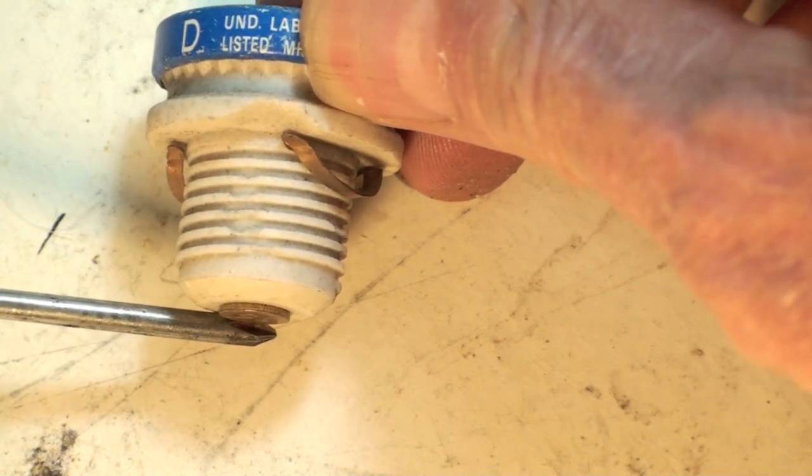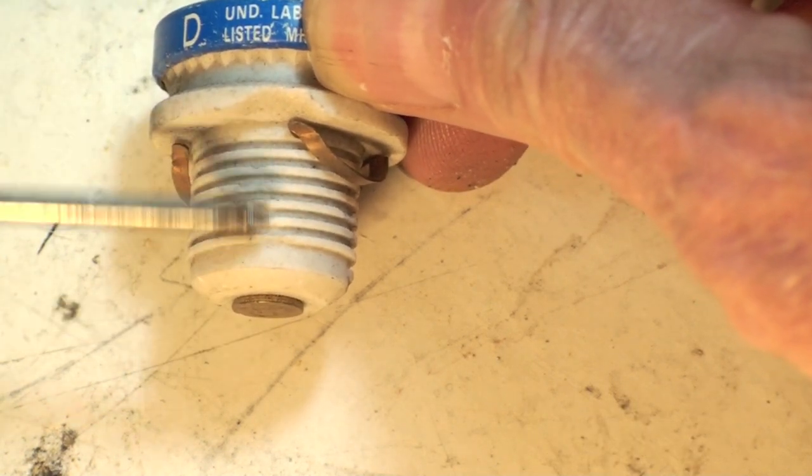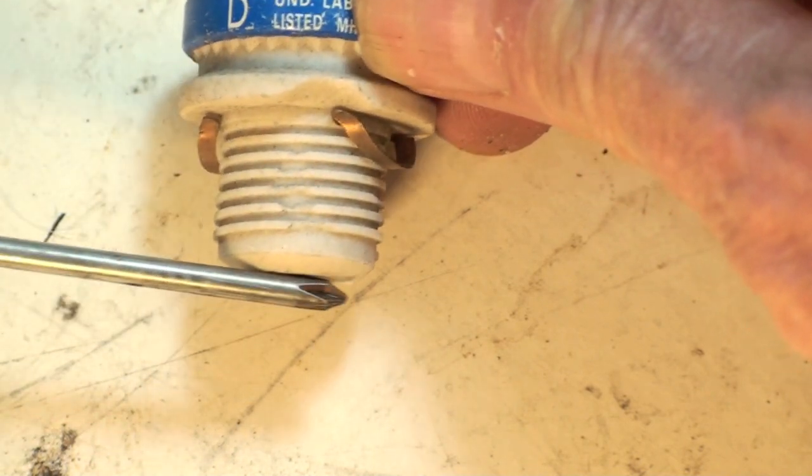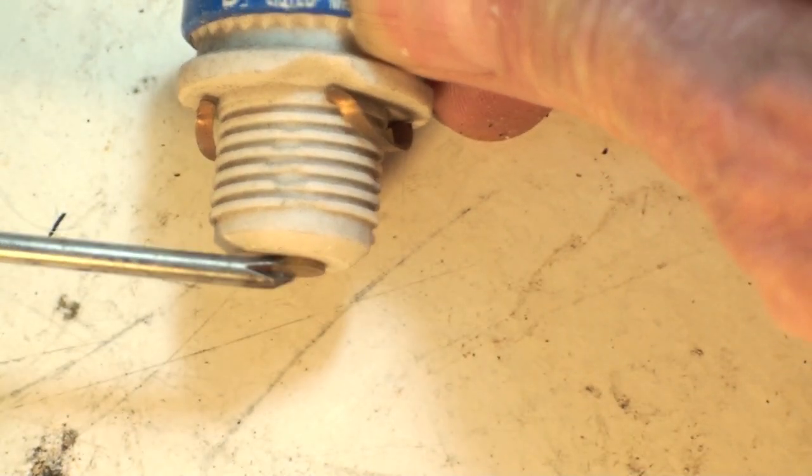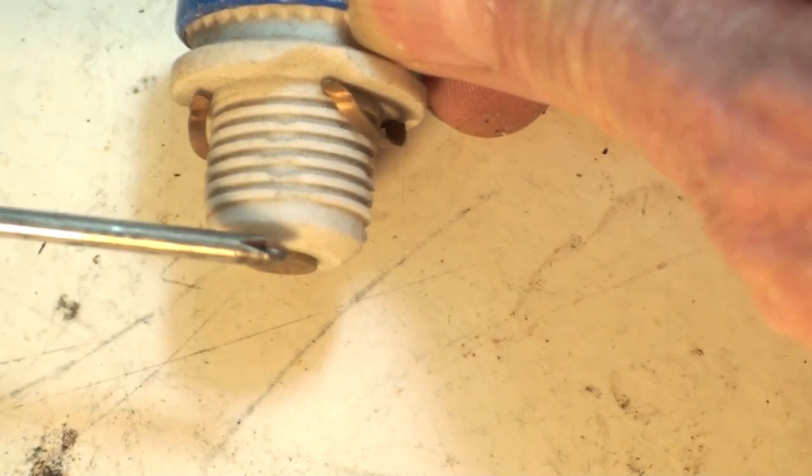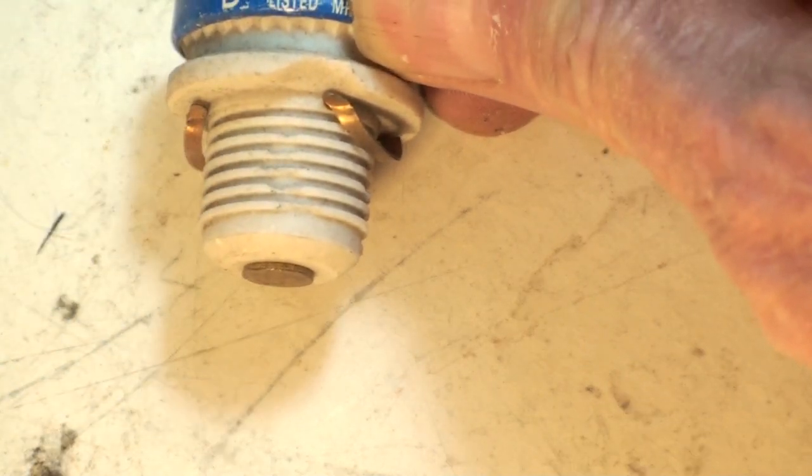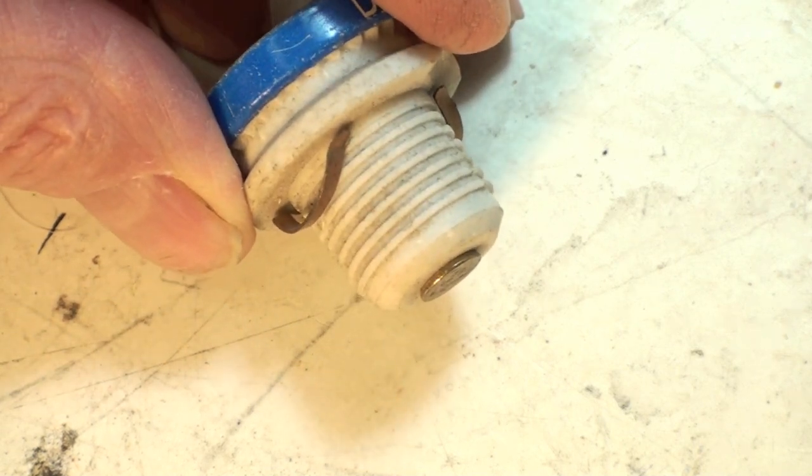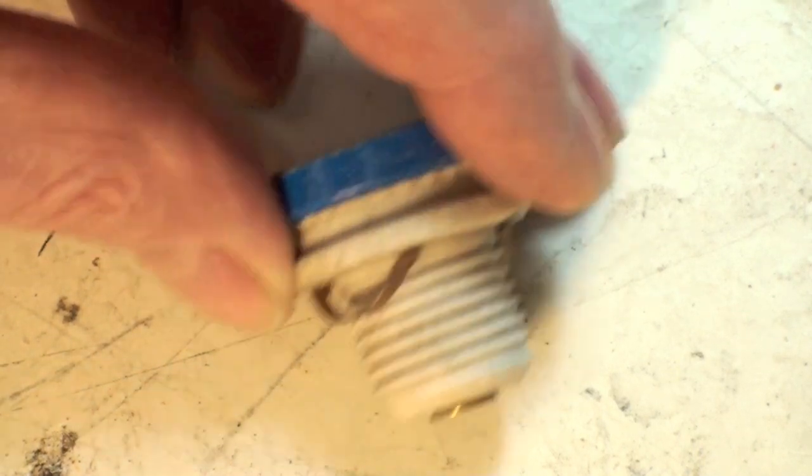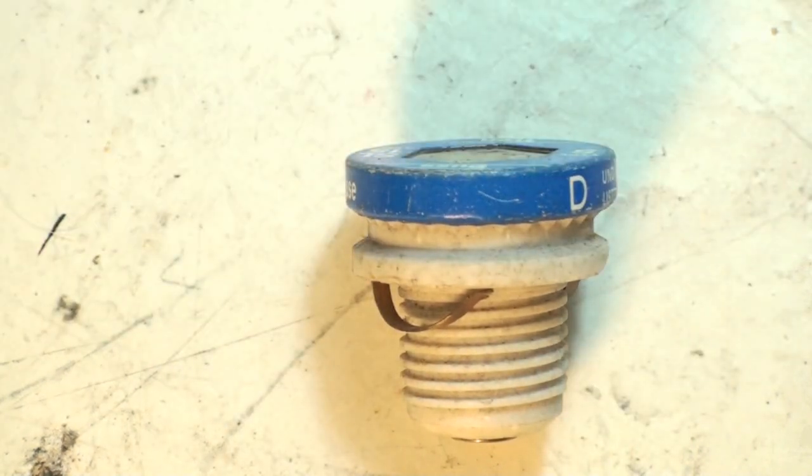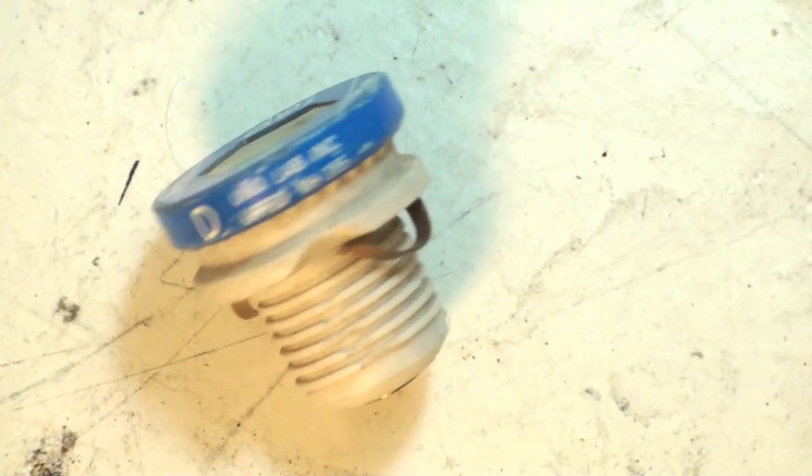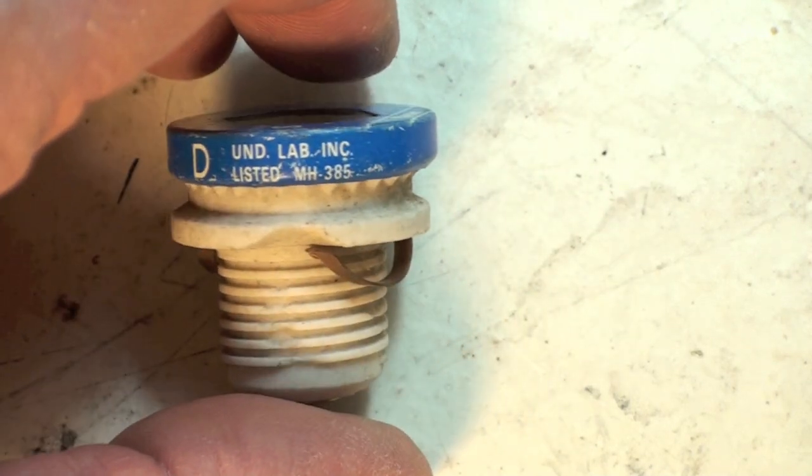Because this is 15 amps, there's a specific distance between here and here. If this was 10 amps, this would not be the same distance, or if it was three and a half amps or five amps. They all had different distances, and so you could screw them in but they wouldn't work.